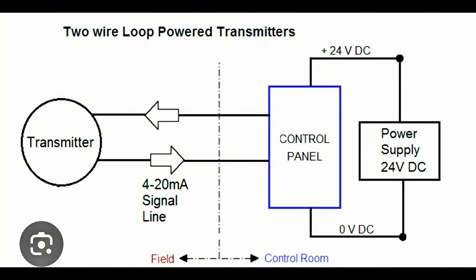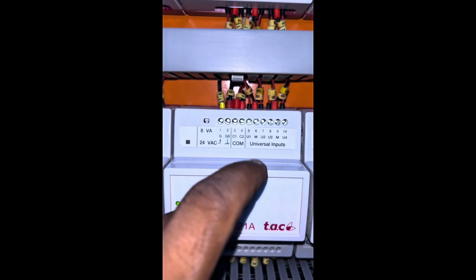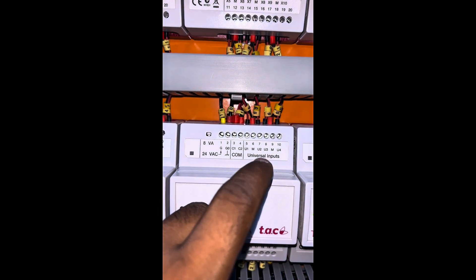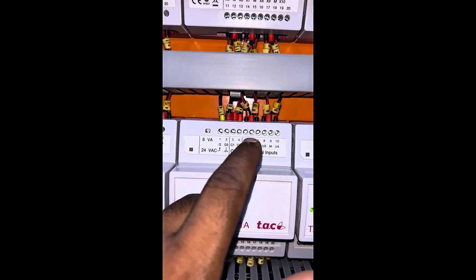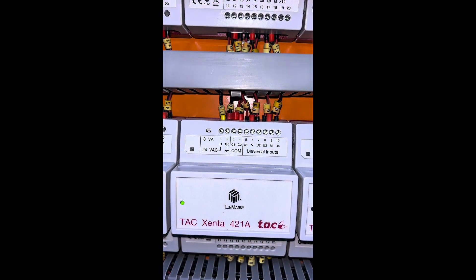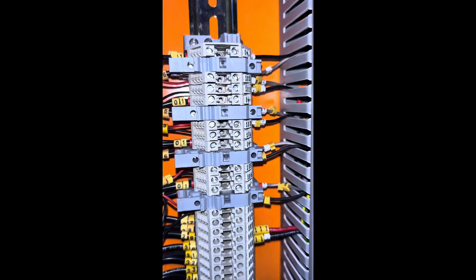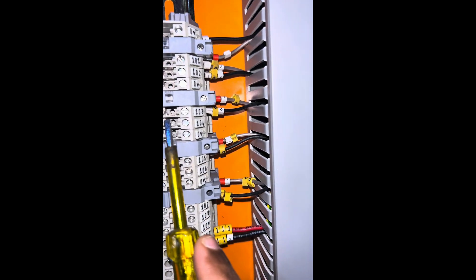The diagram here shows how to connect a 2-wire water level sensor to a controller and transmitter. The transmitter here we use is the water level sensor from Nivelco. This is our controller where the level sensor feedback is connected. Based on the 4-20mA feedback received, it will show in our BMS graphics.